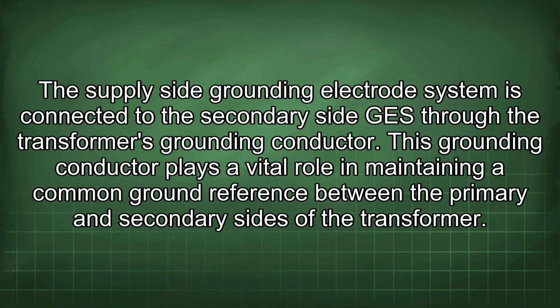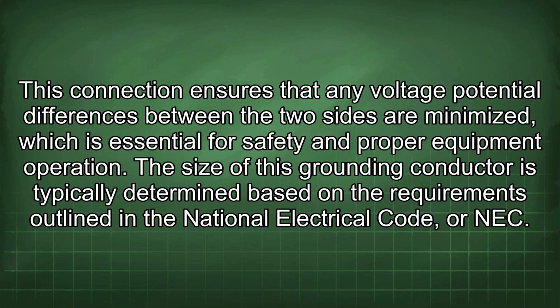The supply-side grounding electrode system is connected to the secondary side GES through the transformer's grounding conductor. This grounding conductor plays a vital role in maintaining a common ground reference between the primary and secondary sides of the transformer. This connection ensures that any voltage potential differences between the two sides are minimized, which is essential for safety and proper equipment operation.